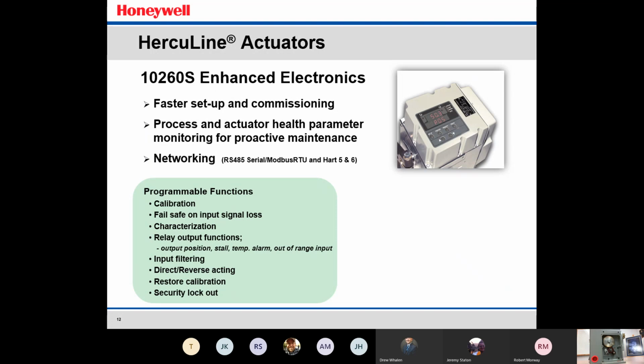The programming functions of the smart enhanced electronics, again, you can do calibrations, so you can calibrate the actuator 0 to 100%. You can set the fail-safe input, so in the event that you lose your 4 to 20 milliamp signal, you can set the actuator to go.